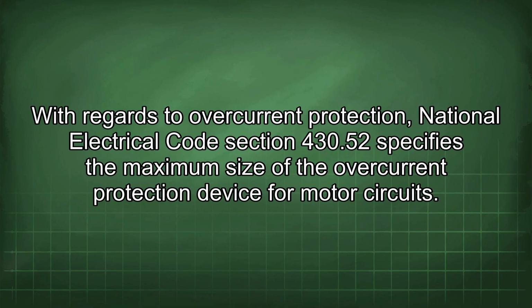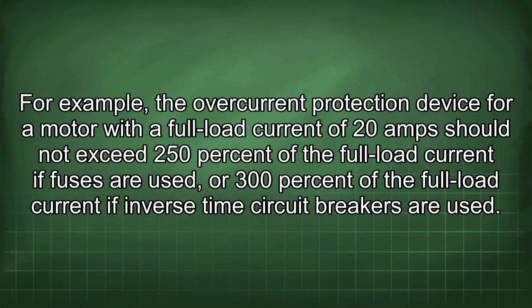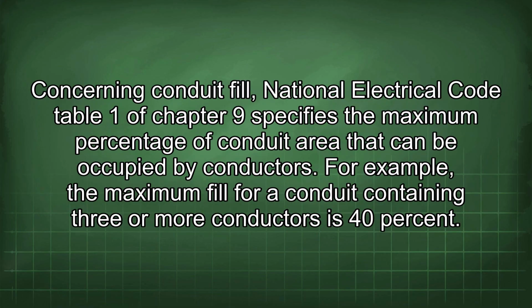With regards to overcurrent protection, National Electrical Code Section 430.52 specifies the maximum size of the overcurrent protection device for motor circuits. For example, the overcurrent protection device for a motor with a full load current of 20 amps should not exceed 250% of the full load current if fuses are used, or 300% of the full load current if inverse time circuit breakers are used. Concerning conduit fill, National Electrical Code Table 1 of Chapter 9 specifies the maximum percentage of conduit area that can be occupied by conductors. For example, the maximum fill for a conduit containing 3 or more conductors is 40%.